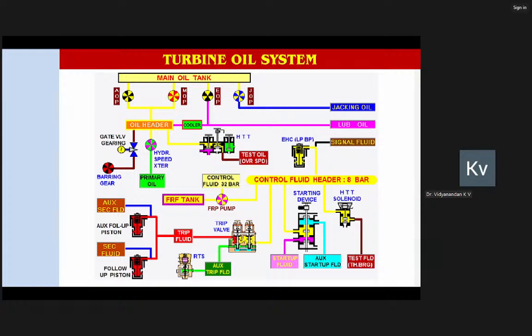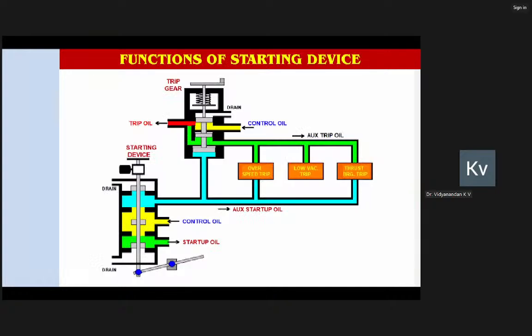And in the latest 660 megawatt and 800 megawatt units, there is only one oil pressure, that is the 160 bar high pressure governor. In your 600 megawatt Siemens unit, you must have the 160 bar high pressure governor, because with increasing pressure, the system becomes more compact and less complex. So here, those 12 different signals you can visualize from this screen. I'm not going to explain all those things because it will take a lot of time.